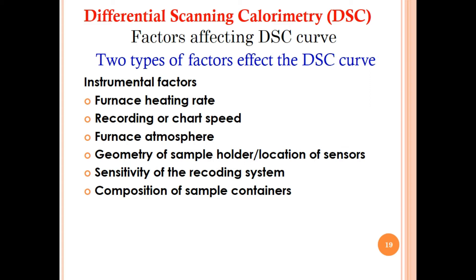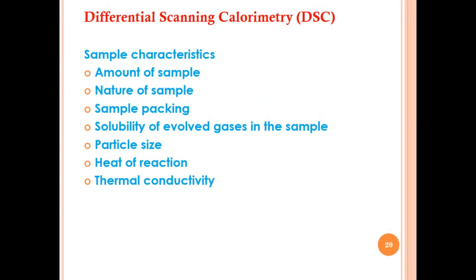We already discussed which type of container must be used — ones that are unreactive with the sample under investigation. The second type consists of sample characteristics, which also affect the DSC curve: amount of sample, nature of sample, sample packing, solubility of evolved gases in the sample, particle size, heat of reaction, and thermal conductivity.